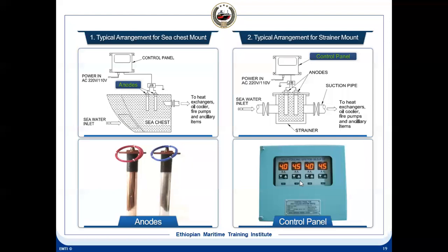So when the anode is almost finished, suppose the anode is finished, then how do you make this out? Then you'll find the current is also falling. The display corresponding to the anode will start falling. Normal life of this anode is around 1.5 years. But if you observe the current is falling, it means the anode is finishing slowly.